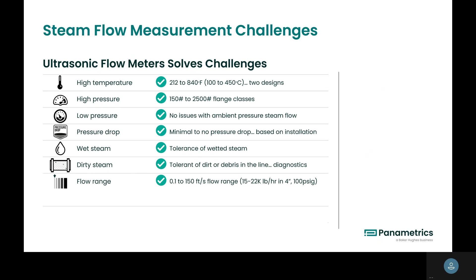Then dirty steam. Again, I use the example of the geothermal application. It's up and running. It's been fantastic overall, and the way we design the transducers and how we insert them definitely helps out for sure. But we also use the diagnostics to do some preventive maintenance. If it's really bad, a lot of coating, we actually can tell you, hey, it's going down. You probably need to do maintenance maybe two months from now or three months from now. But you can start looking at trending some data, which ultrasonics does provide some of those details.